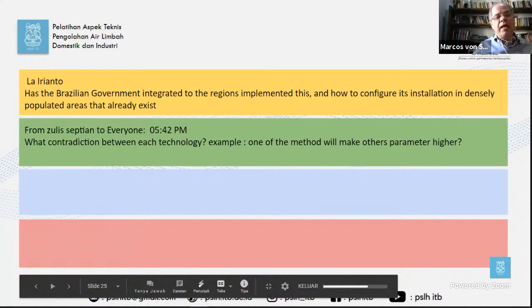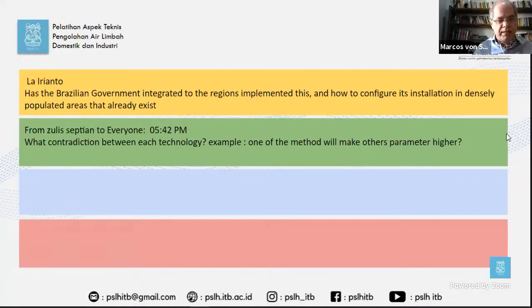And then finally, we also need a good preliminary treatment. Good sand removal, because sand cannot accumulate inside anaerobic reactors. And ideally, in the preliminary treatment, using not only coarse screens and medium screens, but also sieves that remove most of the solids that could lead to the formation of scum. Okay. This is why it's not so simple for very small communities. But if you have from 500 population equivalents upwards, you can handle these.